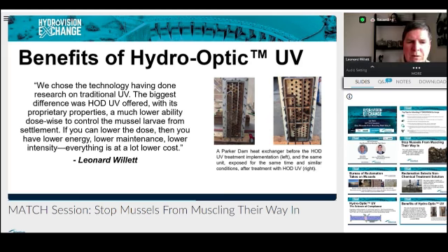It was a turnkey install. We installed it at Hoover, Davis, and Parker dams on the lower Colorado River. Each install was done by a different contractor, which tells you it's very simple to install in your piping system—installed in the cooling water system right after the strainer at each dam. The advantage was that the heat exchangers no longer suffered biofouling and overheating.